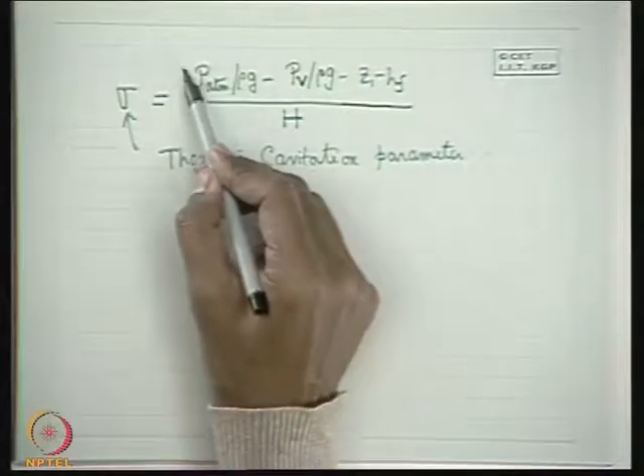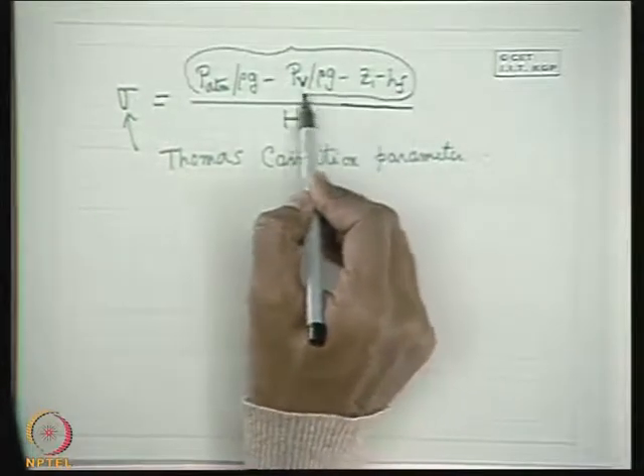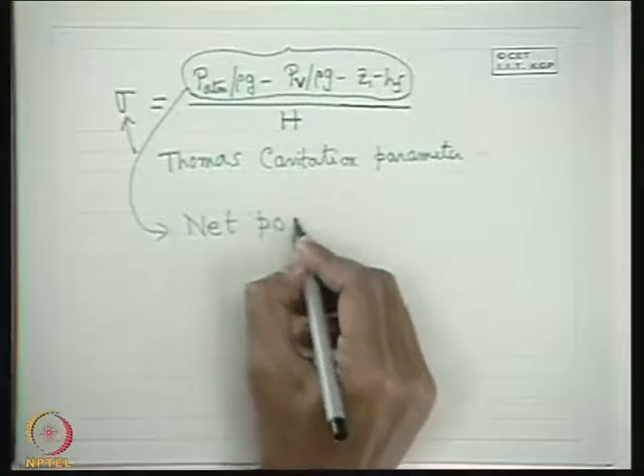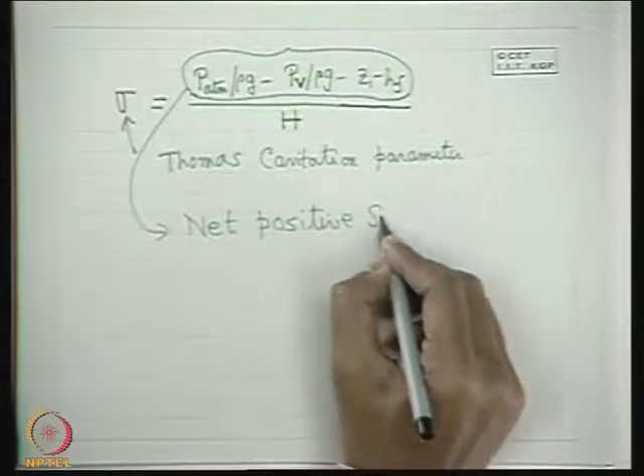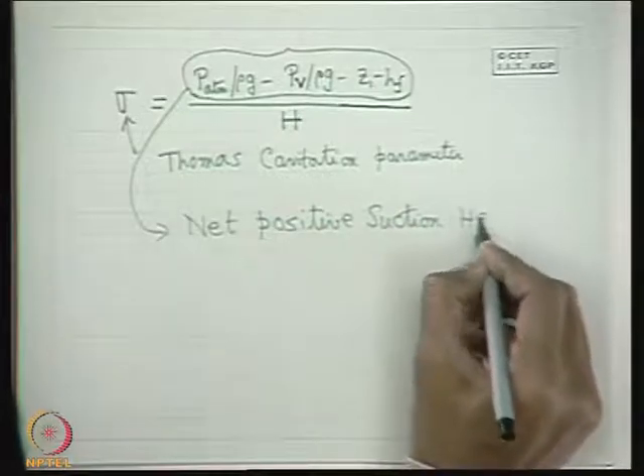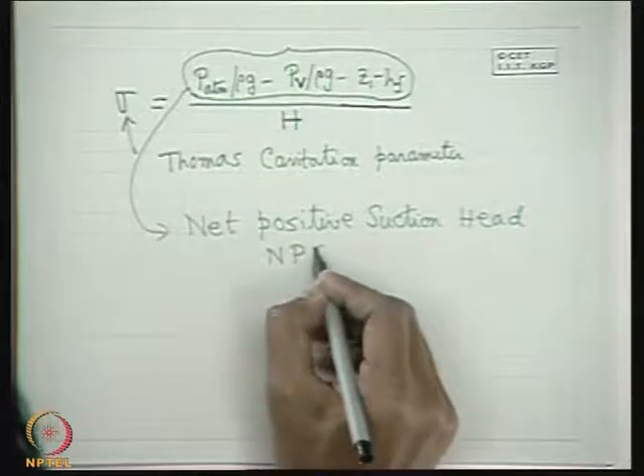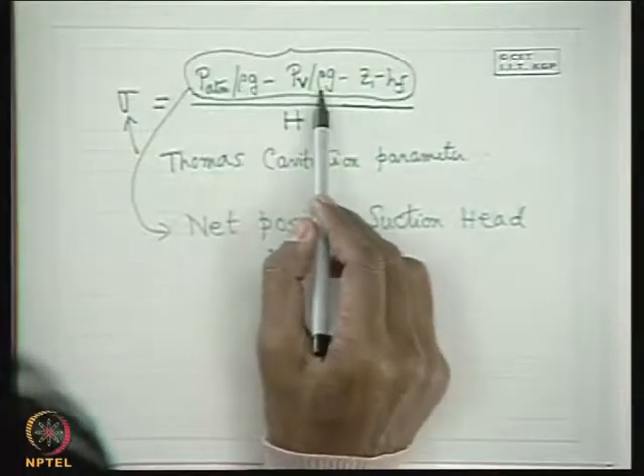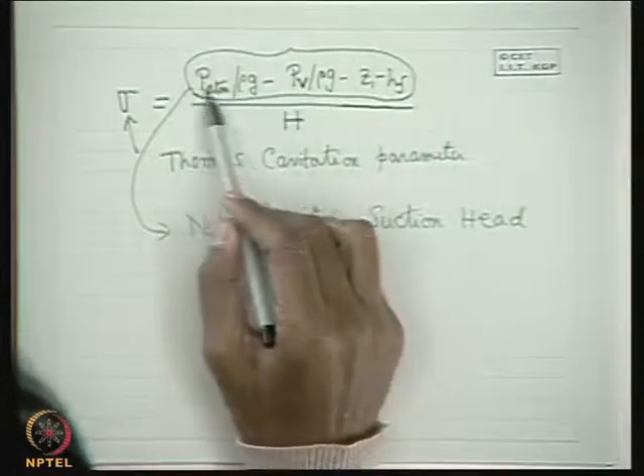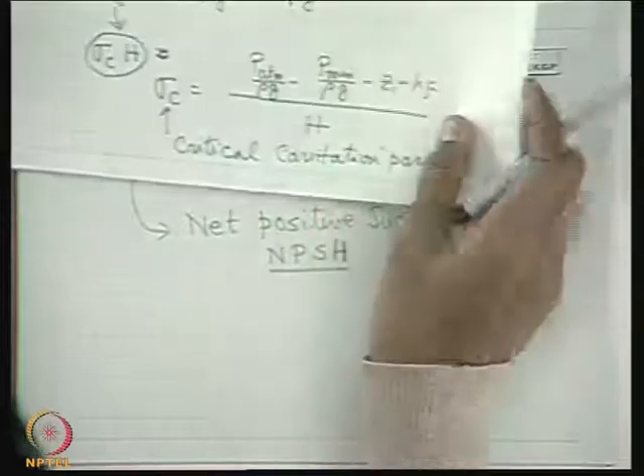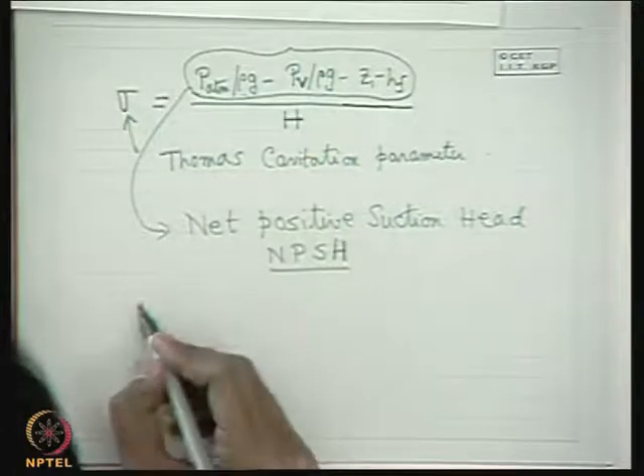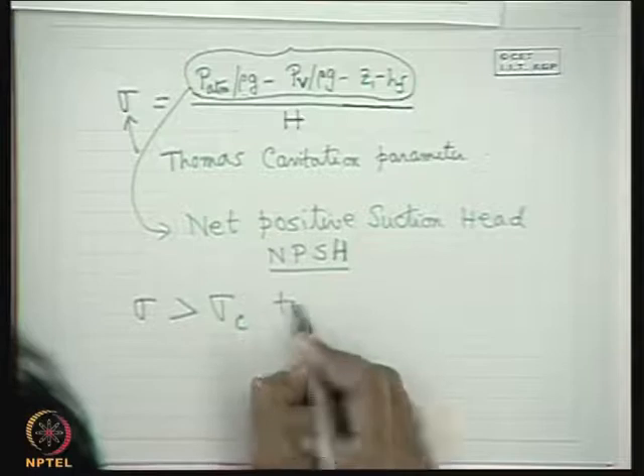The numerator of the Thomas cavitation parameter expression — [p_atm/(ρg) − p_v/(ρg) − z₁ − h_f] — is known as the Net Positive Suction Head (NPSH). The condition to avoid cavitation is that σ must be greater than σ_c, meaning the pressure at the impeller inlet must always remain higher than the vapor pressure.